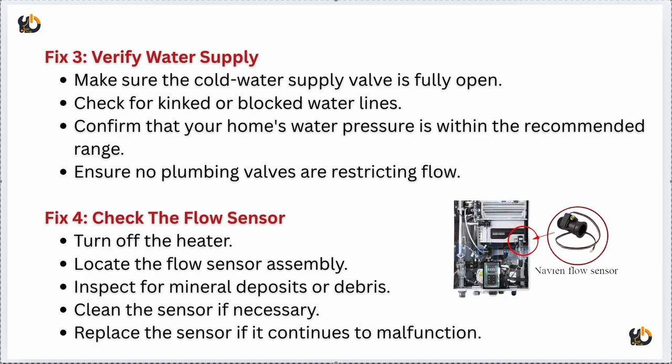Fix 4: check the flow sensor. So turn off the heater, then locate the flow sensor assembly, inspect for mineral deposits or debris, and clean the sensor if necessary. Then replace the sensor if it continues to malfunction.